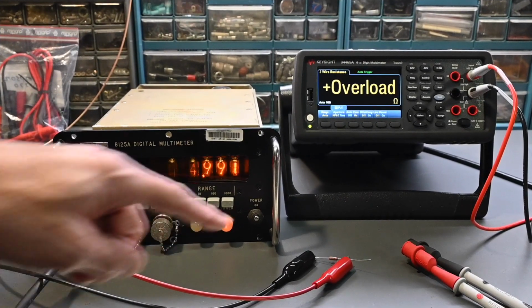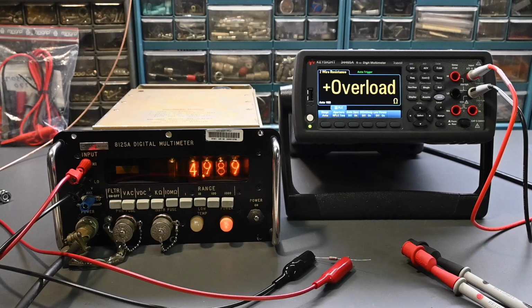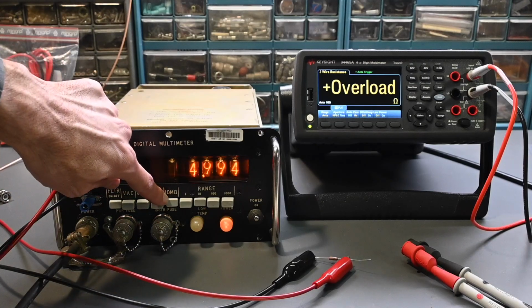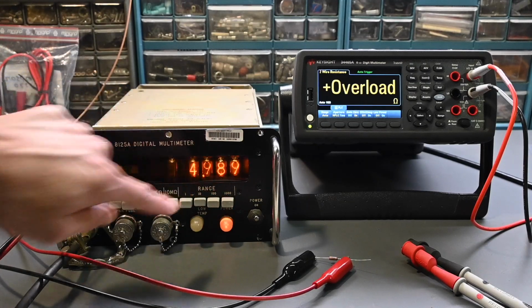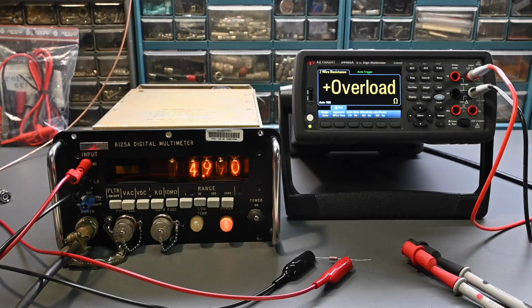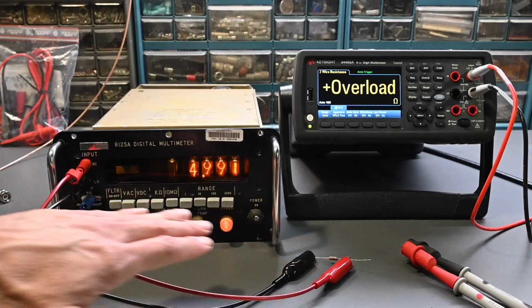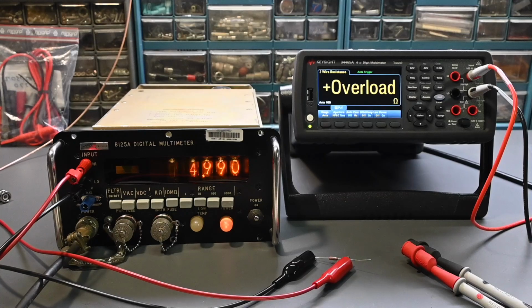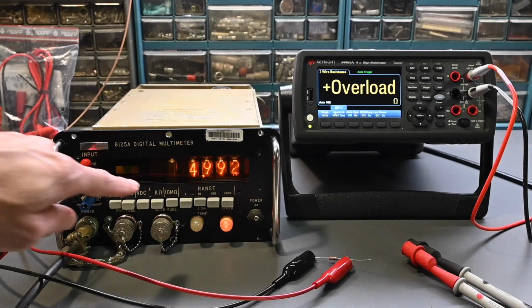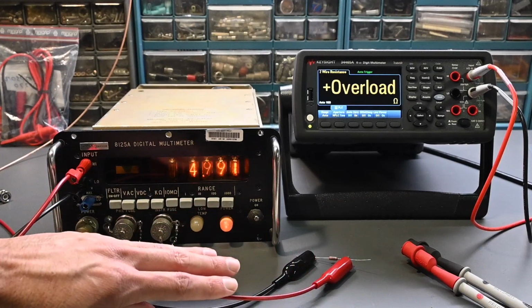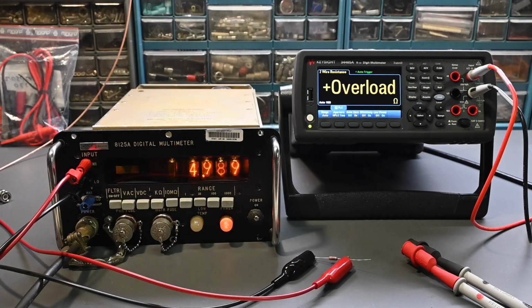All right, I now have a 5 megohm resistor connected to the Fluke 8125A, and this is in the 10 megohm setting, so in 10 megohms, these range switches are no longer used. So you can see when I bring my hand near this, it causes the numbers to change a little bit, so the reading fluctuates slightly, and then it settles back down. And I noticed that when I was doing the calibration on this 10 megohm setting that it's very sensitive to the test leads, being near anything or moving. So it's just very, very sensitive. But again, a 5 megohm resistor, and it's showing 4.99 megohms. So very, very close to the expected value.